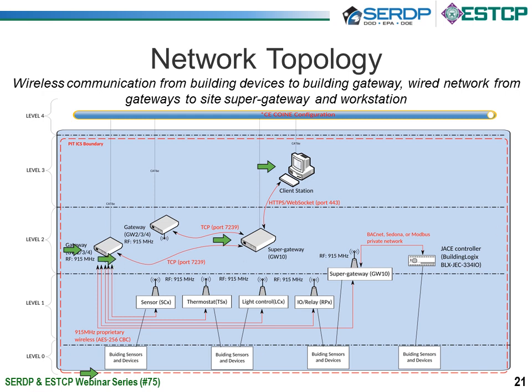So the system is really only wireless for this last leg, and depends on the wired existing networks there at the facility. But this works very well because there's already networking typically wired between the different buildings at these DoD facilities. So we're mainly looking at trying to save the cost of wiring these individual sensors and controls in the actual building.